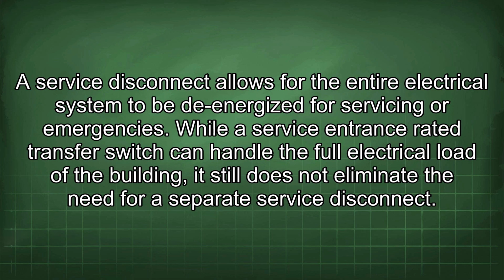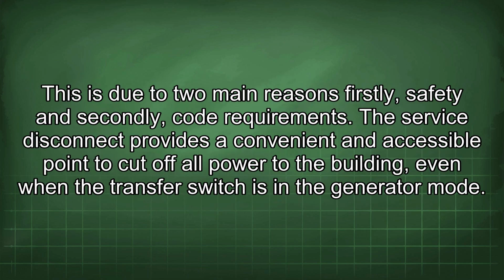While a service entrance rated transfer switch can handle the full electrical load of the building, it still does not eliminate the need for a separate service disconnect. This is due to two main reasons: firstly, safety, and secondly, code requirements. The service disconnect provides a convenient and accessible point to cut off all power to the building, even when the transfer switch is in the generator mode.